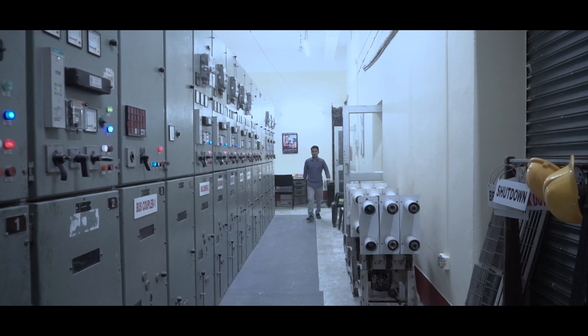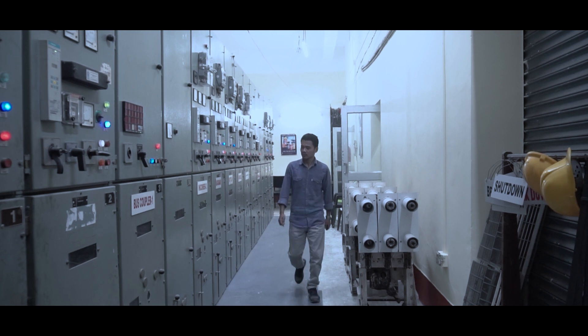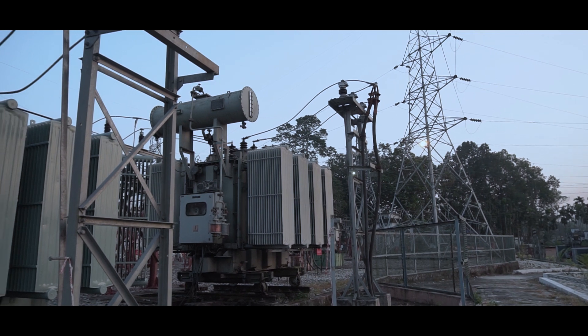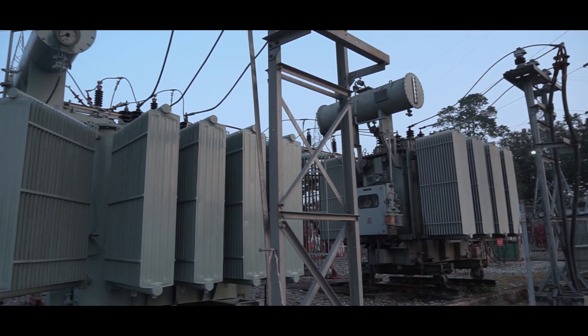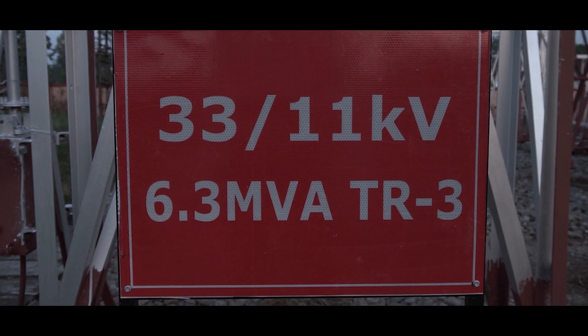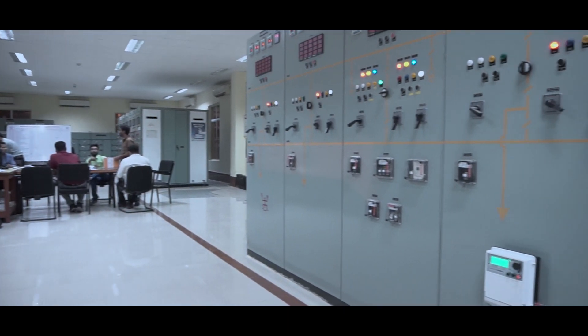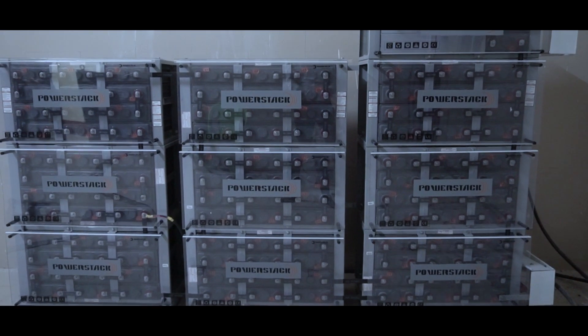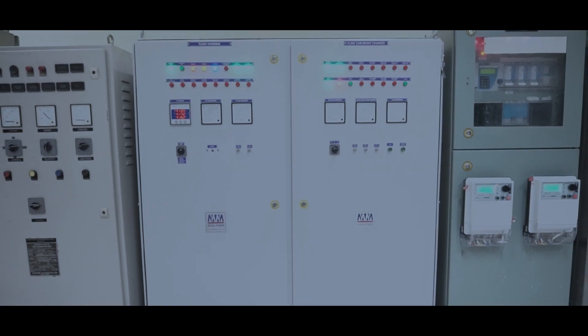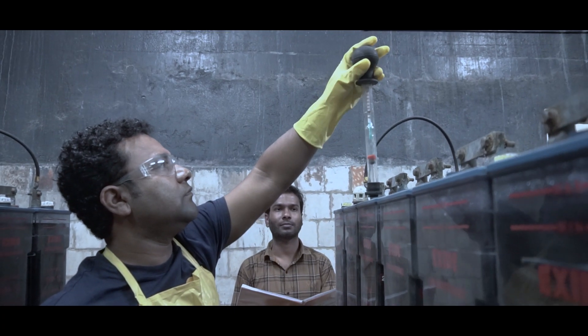The 11kV system at Chalsa is extremely important as it feeds power directly to numerous resorts and places of repute frequented by VIPs and dignitaries. In order to improve reliability and keeping in mind the increasing load demand, a third 33/11kV transformer having the capacity of 6.3 MVA was added to the system recently. As part of ongoing efforts in WBSETCL for increasing the redundancy and robustness of the control system, second sets of 220V DC and 30V DC systems have been incorporated at Chalsa. The battery bank and battery chargers are well maintained.